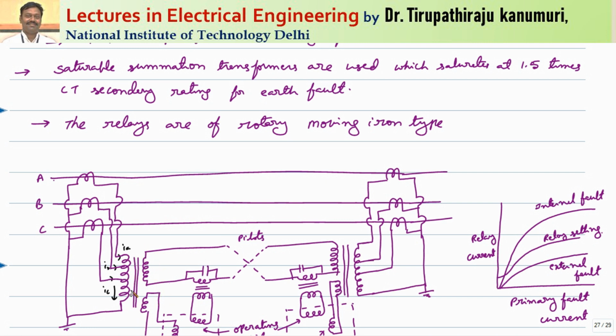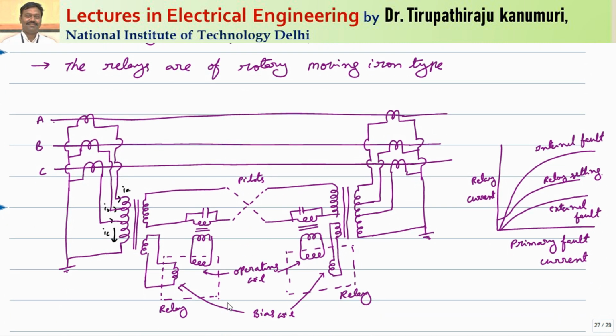There will be two secondary windings. One winding is connected to the pilot wires and the other winding will be connected to the bias coil. We are going to discuss that. Here the transformer is a saturable summation transformer, arranged to saturate at around 1.5 times the CT secondary rating for an earth fault. So under earth fault conditions, at 1.5 times the rating of your CT, the core will saturate in order to protect your remaining devices from damage. That care will be taken, and the characteristic will be like this. For an external fault it will respond like this, and for an internal fault it will respond like this, and the relay setting will be set in between, so your relay will operate.